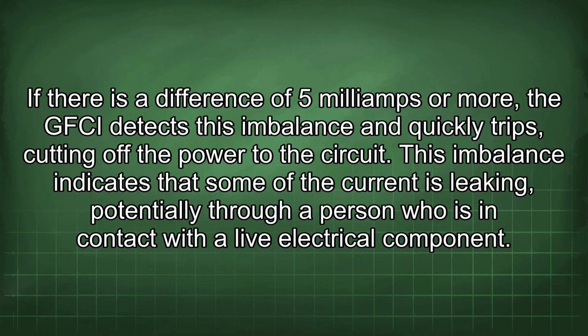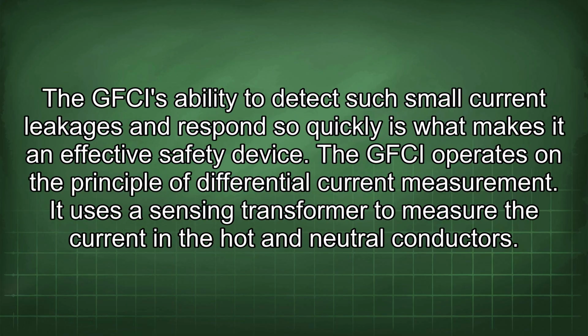This imbalance indicates that some of the current is leaking, potentially through a person who is in contact with a live electrical component. The GFCI's ability to detect such small current leakages and respond so quickly is what makes it an effective safety device. The GFCI operates on the principle of differential current measurement.